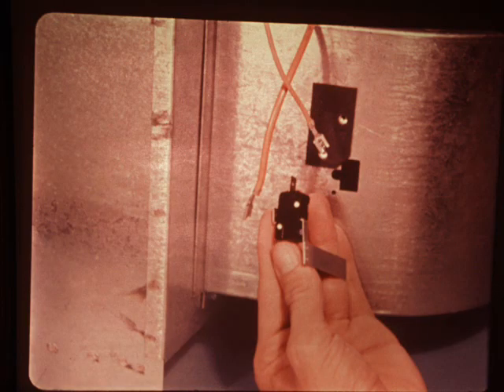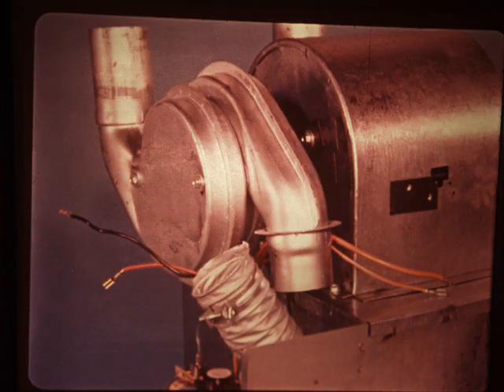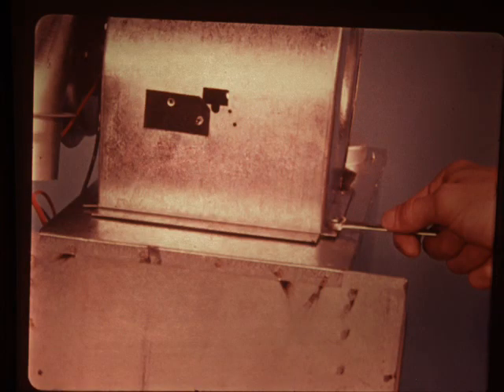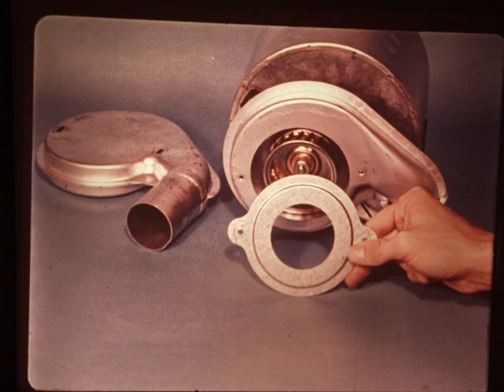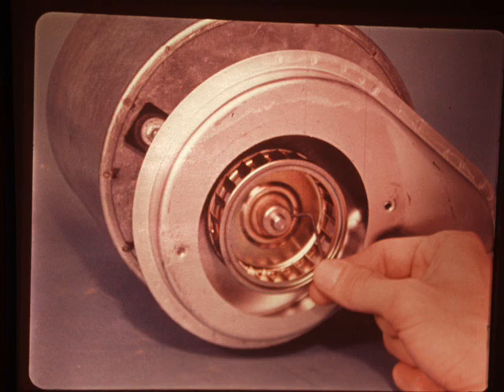To remove the blower motor, first remove the sail switch from the bottom of the blower assembly. Disconnect the motor electrical leads and the flexible air duct from the blower. When you remove the 3 blower mounting screws, you can lift the blower assembly out of the furnace. Remove the outer combustion air housing and the metal plate between the inner and outer housings by removing the 2 attaching screws. Use a 5/64 Allen wrench to remove the combustion air blower wheel.